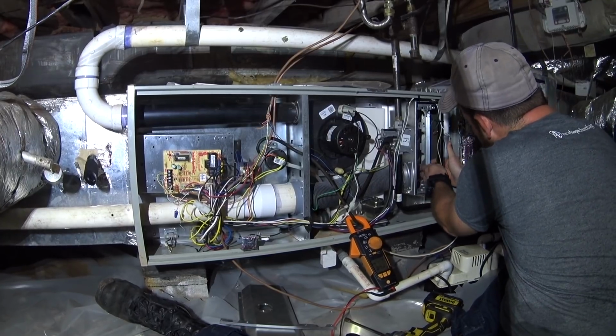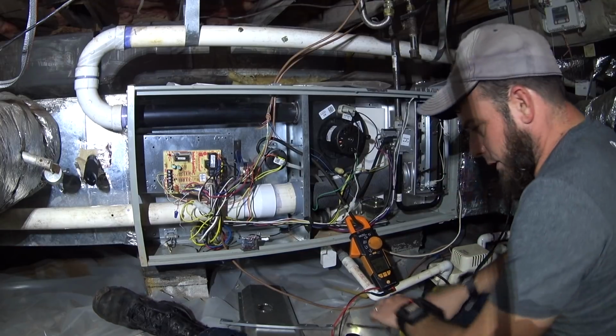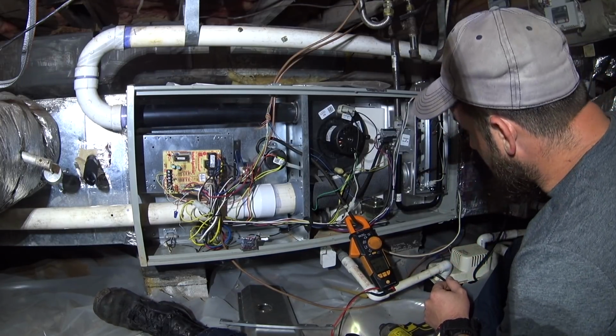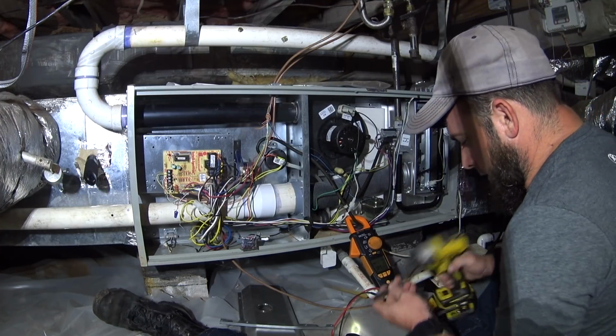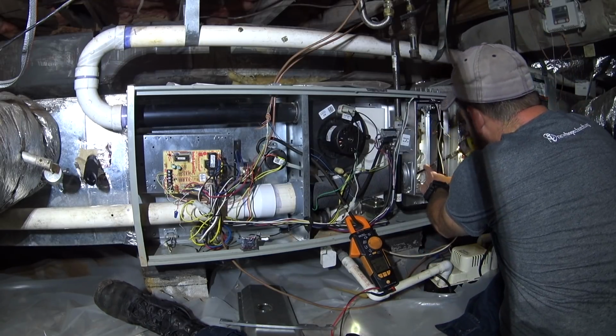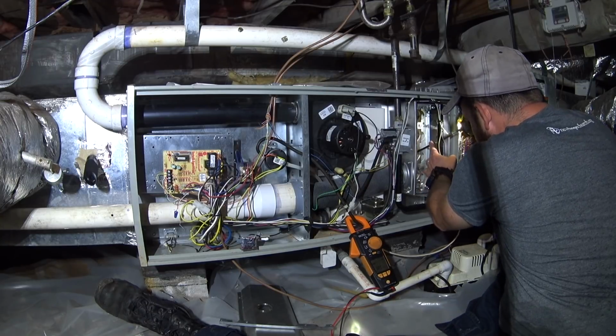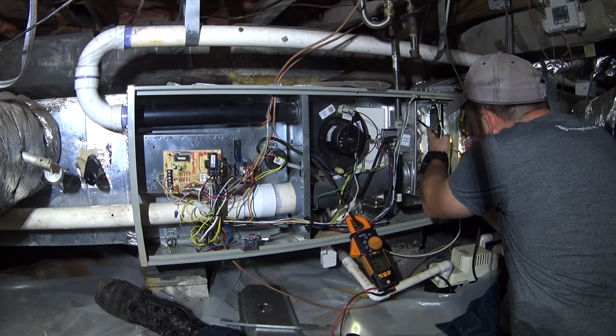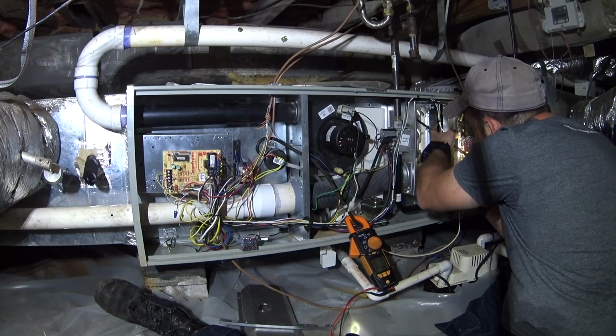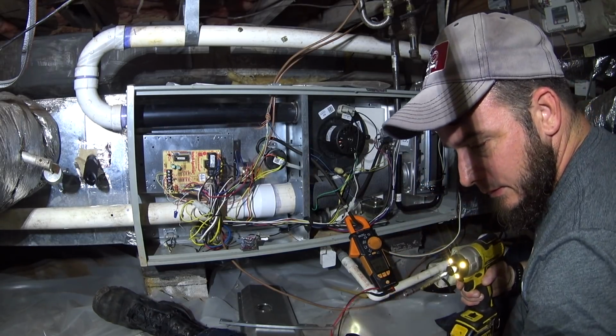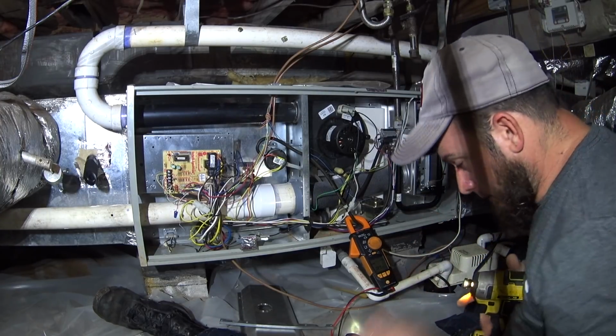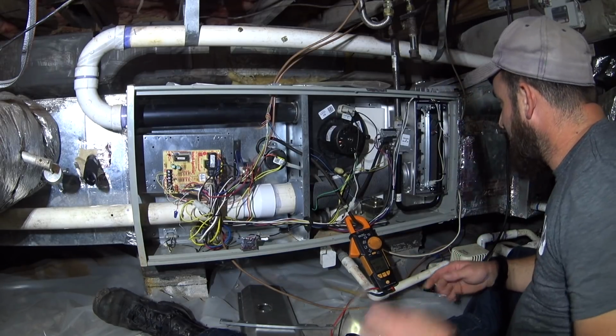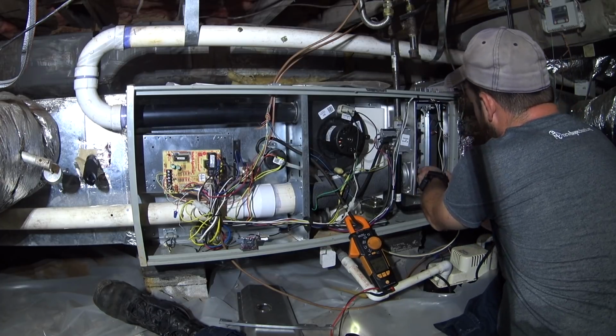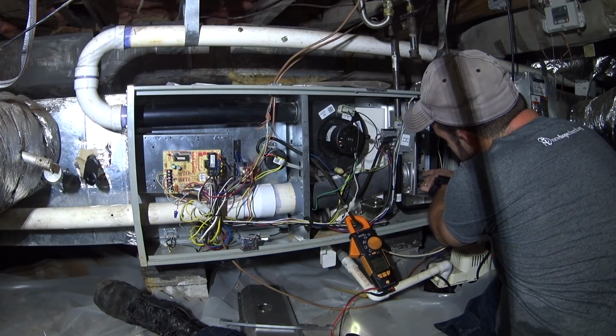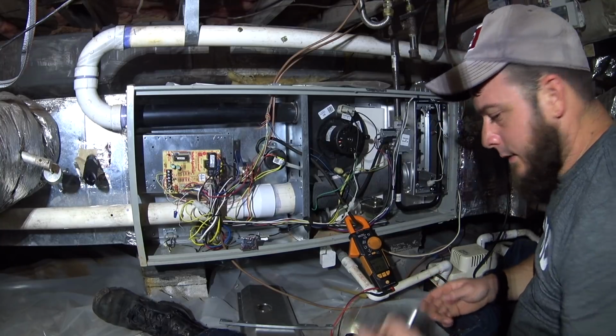That's bothersome that it either somebody loosened them or somehow they became loose on their own, and I can't imagine that there's nearly enough vibration to do that. It just seems unlikely. But with as easy as they are to access with the burners out, it wouldn't surprise me if someone did at one point take them loose. But despite the fact that they're loose, they have not shown any indication of affecting combustion or indicating a potential crack in the heat exchanger.